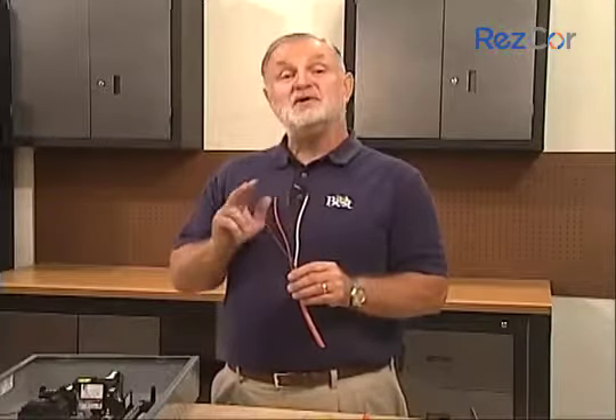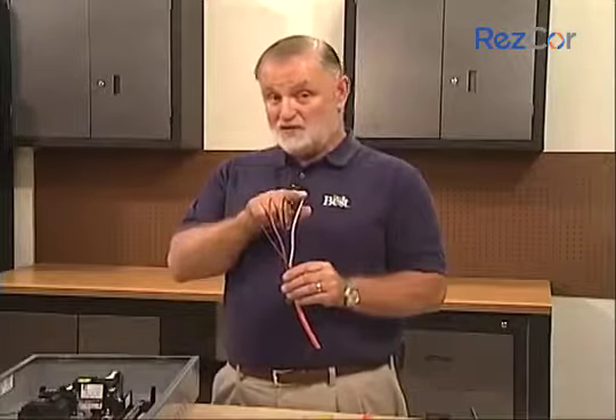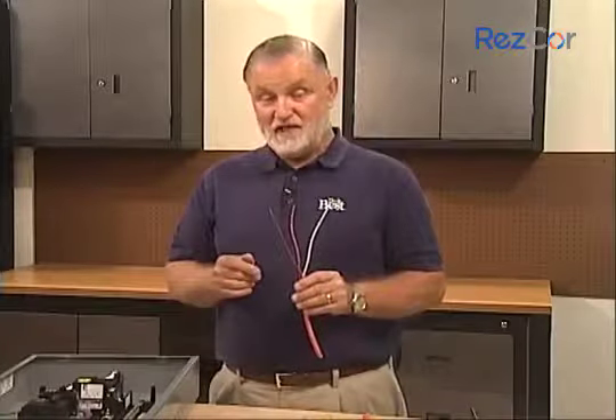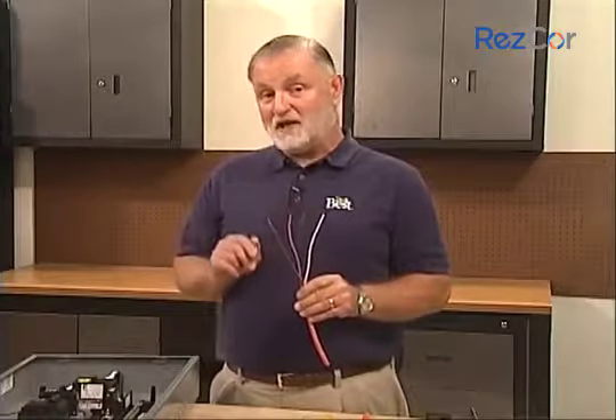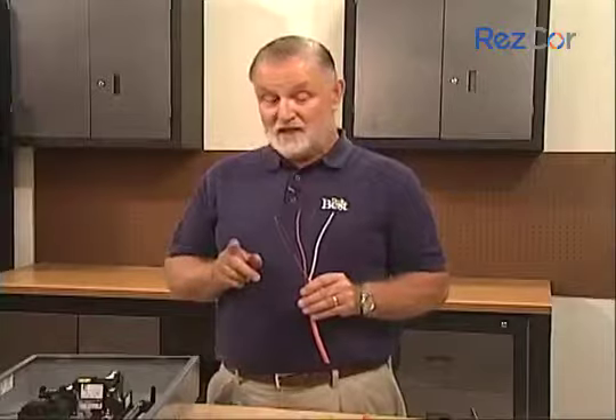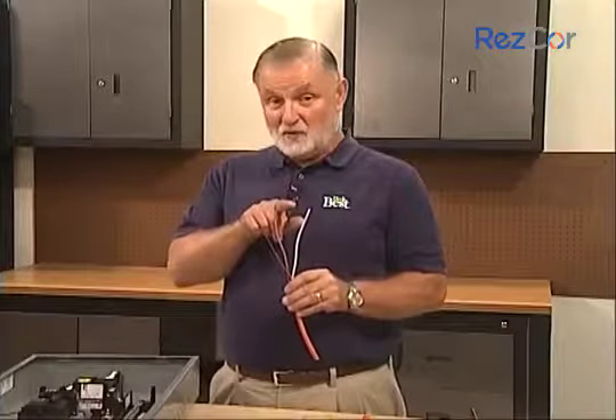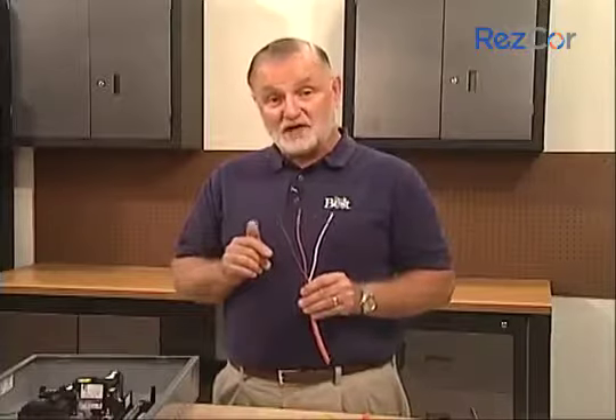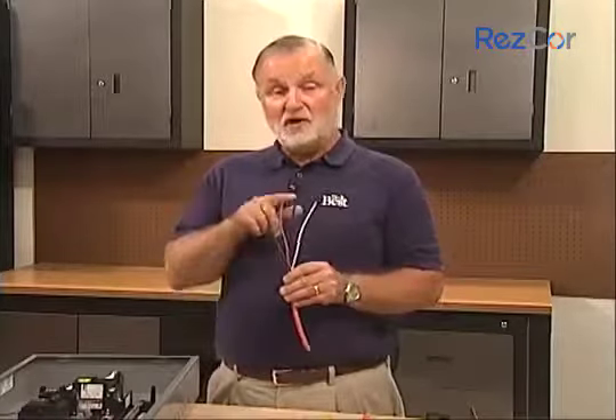Ranges and dryers use both 120 volts and 240 volts. When you operate such a device, you need 3 conductors because you need 2 hot wires to run the 240 volt device, and you need the white neutral wire to run the 120 volt device. Let's consider a clothes dryer as an example. The 2 hot wires, red and black, supply power to the 240 volt heating element. The white neutral, along with one of the hot wires, operates the 120 volt timer and any other 120 volt devices on the dryer. It doesn't matter which of the 2 hot wires you pick to run 120 volts to a device, since they both contain the same voltage pressure.